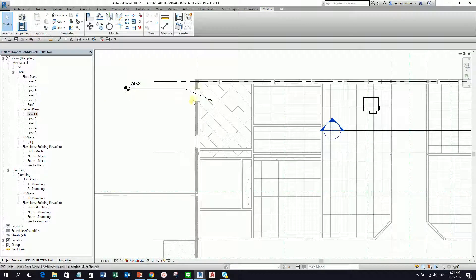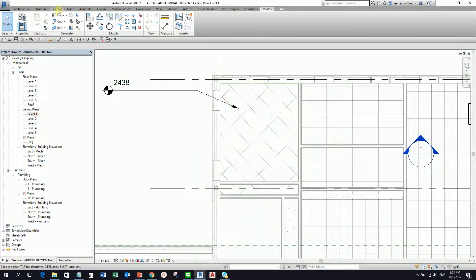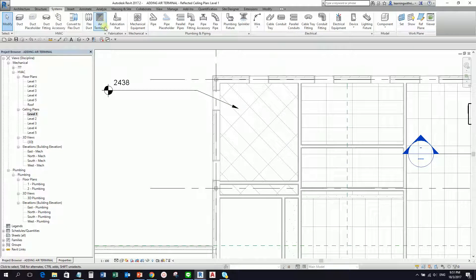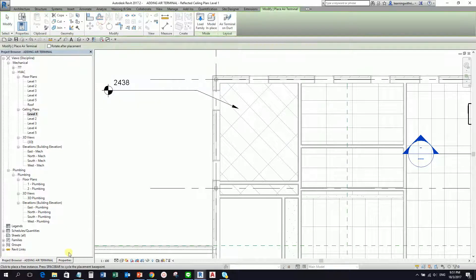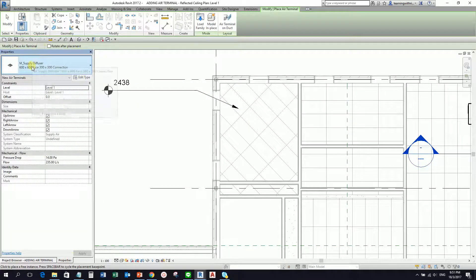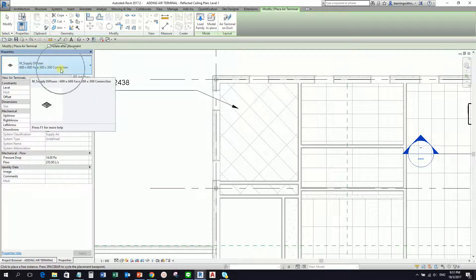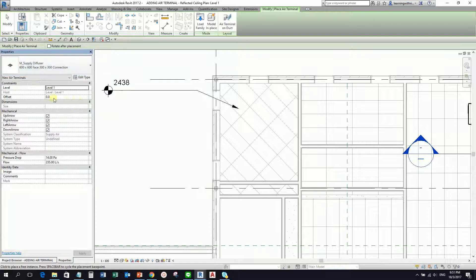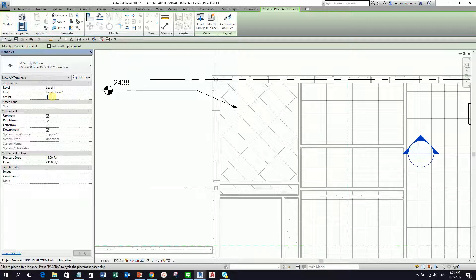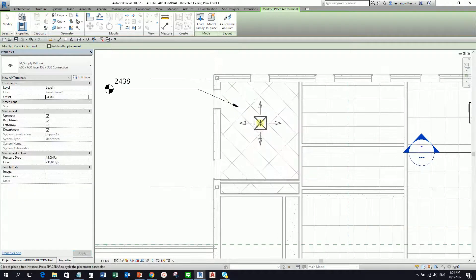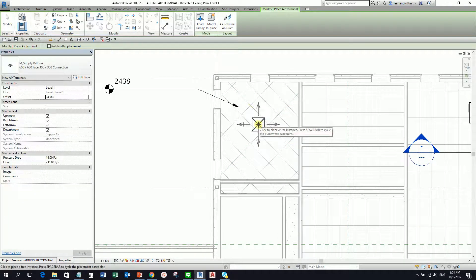From the Systems tab, I'm going to select Air Terminal. I'll place a Supply Diffuser 600 by 600 face, 300 by 300 connection. The offset I'll set to 2438 — the same height as our ceiling. With the correct offset, you will now be able to see your air terminal on the ceiling plan.